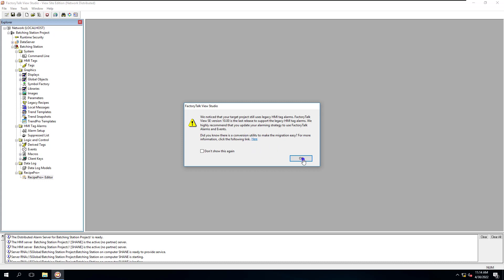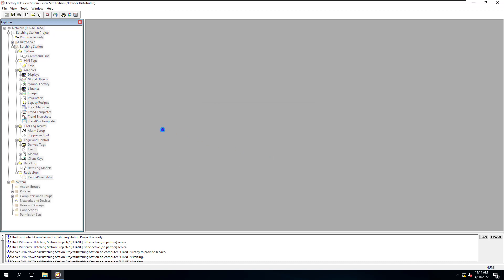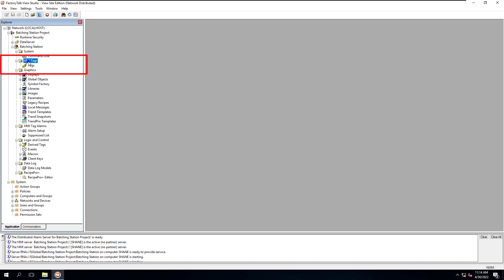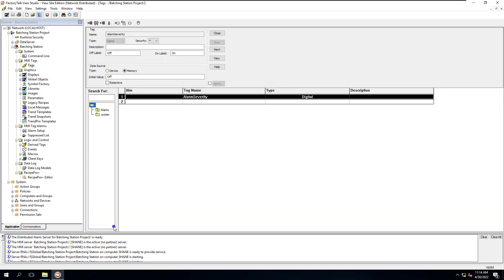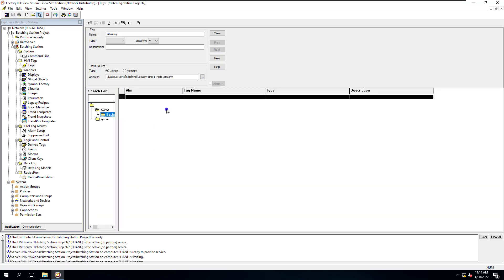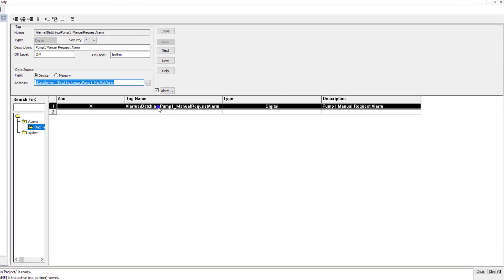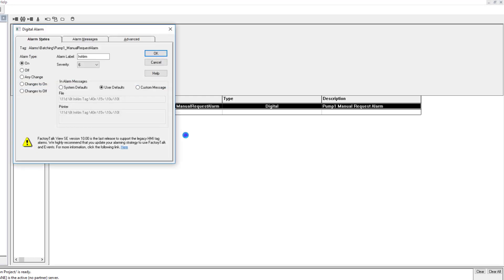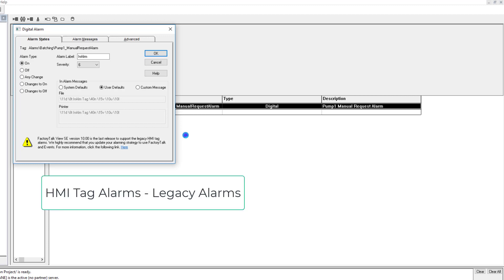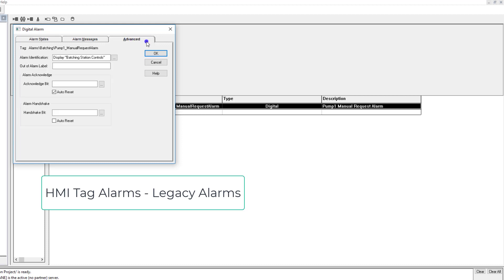We're going to click OK. We actually have one of those HMI alarms in our system — I added that just to give you this instance. What they're talking about is HMI tags right here — tags that have an alarm configured, meaning you're using the legacy tag alarm. I'll pop that open and show you. You can see I have this alarm under my HMI tags, and that's no longer going to be supported after Factory Talk 10, meaning Factory Talk 12 or above, it's no longer going to work.